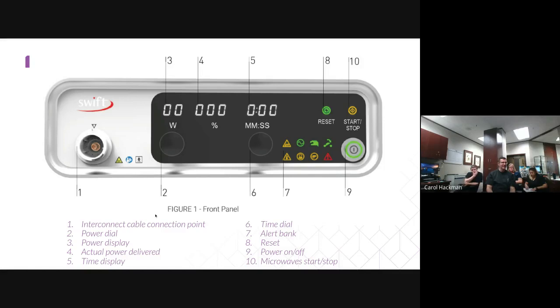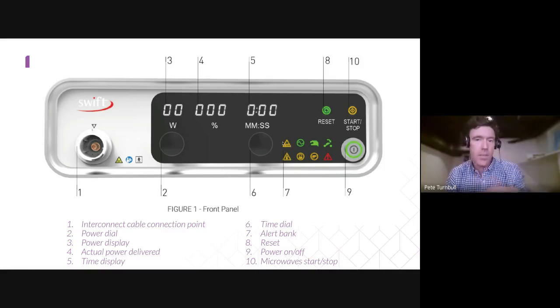Okay, say that one more time. So if you ever get a reflection error, so the patient pulls away and you can't finish the 2-second dose, the system will actually stop, and you'll get this reflection error. This will pop up, and you'll see it on the system. What that means is that not all of the energy was delivered, so it tried to return the energy back to the system. What you do there is hit reset, and then you adjust your time back to 2 seconds, and you do your treatment again and finish your dose. So it's just a way for the system to say, if the patient pulls away, we're not transmitting microwaves openly in the office. It just stops it. And that triggers when this percentage falls below 80%.